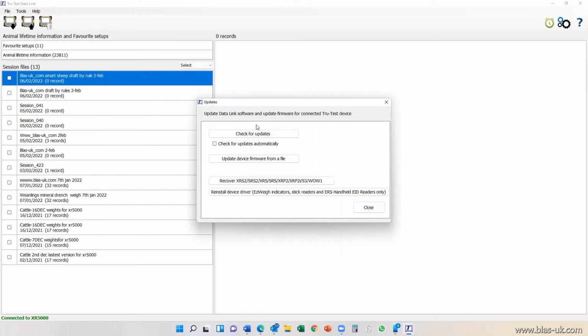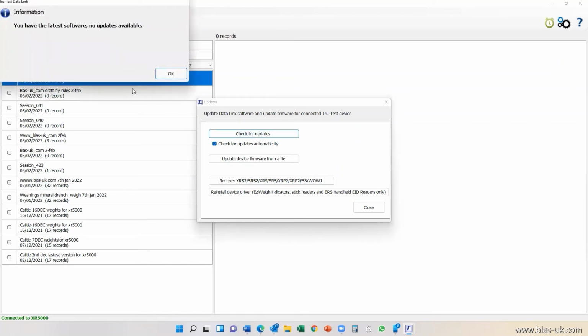Sometimes when we update the Tru-Test devices, the third-party management software are not aware of this, and this can give us issues with trying to download or upload into the Tru-Test device from the third-party software. But if you're using a software that uploads from a CSV file, I would recommend you have it on automatically check for updates. To check for updates manually, or to check to make sure there's no updates missing, just click check for updates, and we can see here there is no updates available for this device.